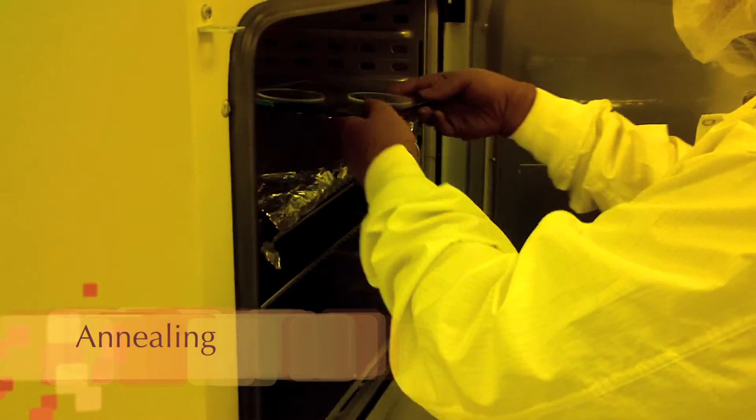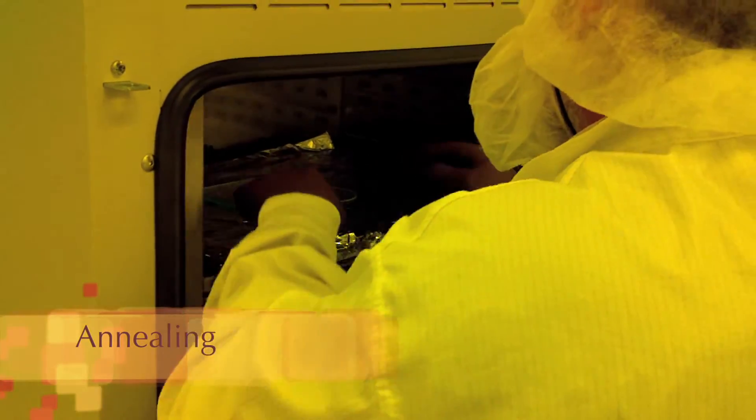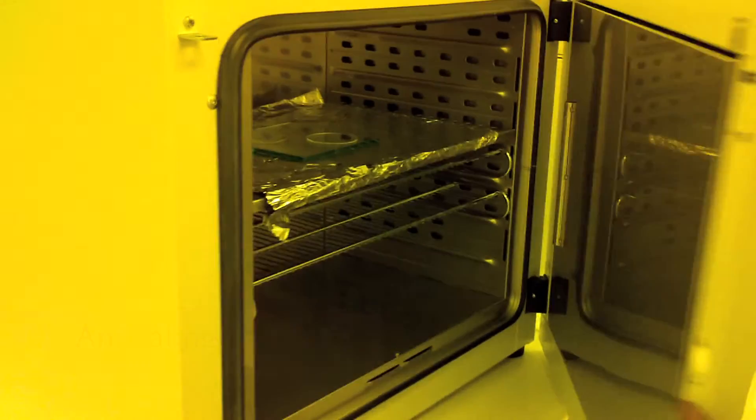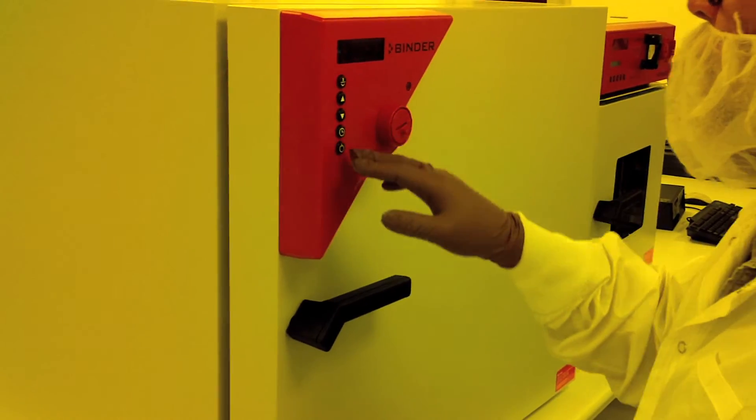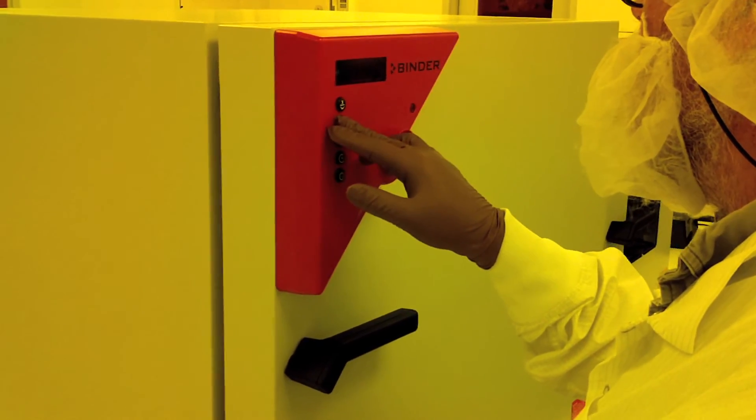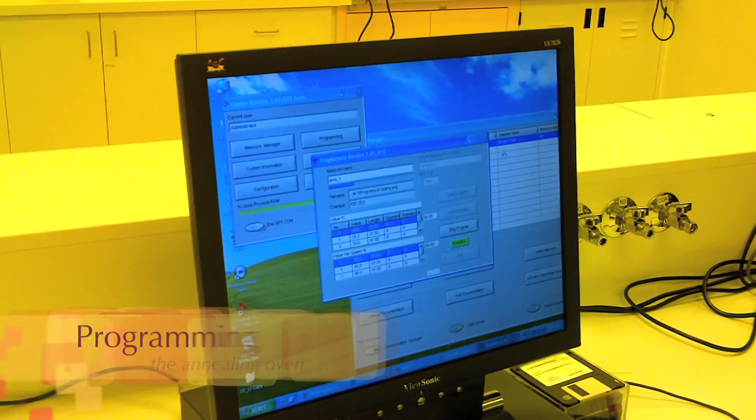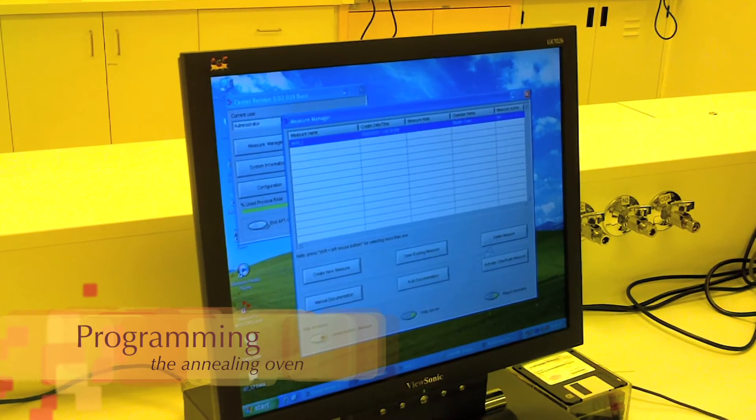The cut PMMA is then annealed in a vacuum oven at 110 degrees Celsius in a programmed sequence to remove any residual stress in the polymer sheet before it is glued onto the substrate. This step is critical as it will avoid future delamination issues from the substrate and prevents cracks forming in the resists.